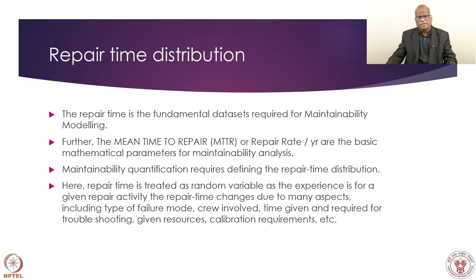There is a useful analogy between reliability and maintainability. In reliability we have failure rate; in maintainability we have repair rate. In reliability we have mean time to failure (MTTF); in maintainability we have mean time to repair (MTTR). The inverse of mean time to repair is the repair rate. The mean time to repair and repair rate are the fundamental mathematical parameters for maintainability modeling.